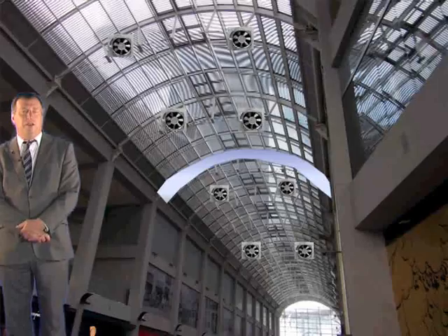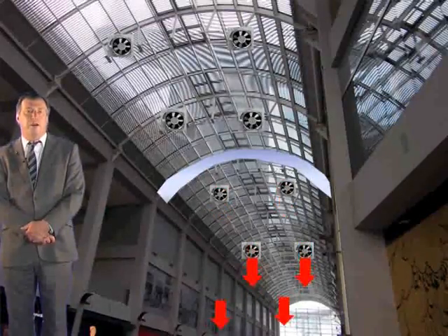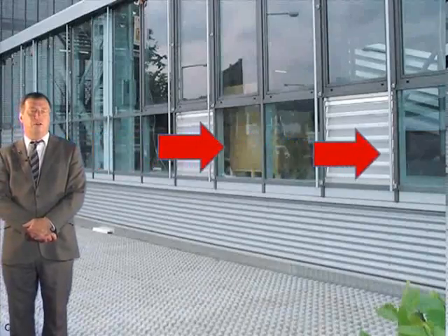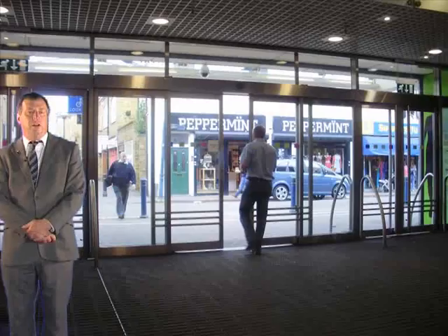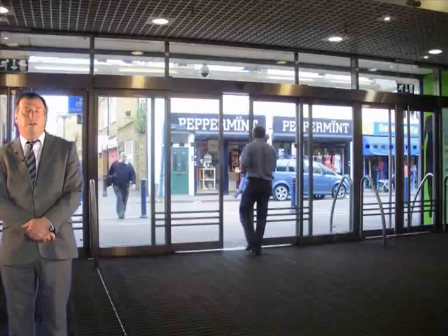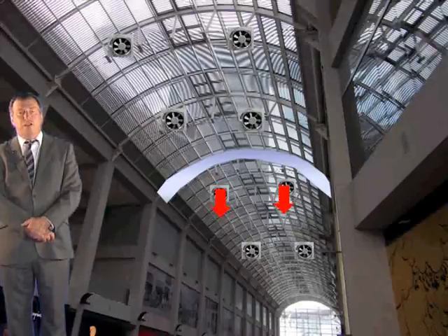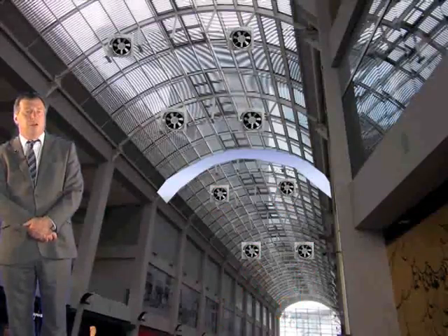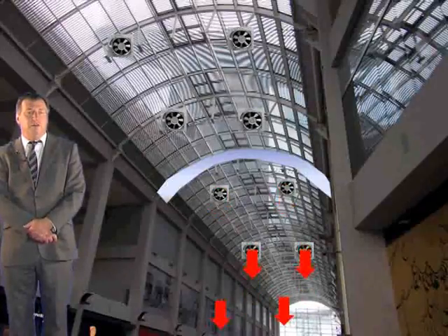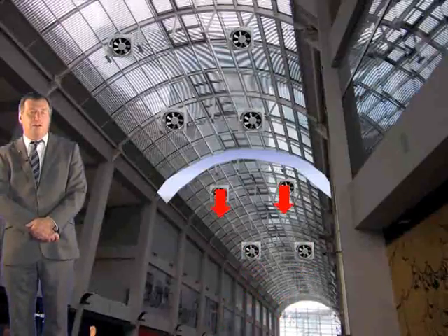These might be the ventilators in smoke reservoirs that are unaffected by the fire, or they may be automatic opening vents located at low level in the walls of the building, or they might be the doors that are used for means of escape, doors that automatically open on actuation of the smoke control system. Natural vents in unaffected smoke reservoirs can often be opened automatically at the same time as the vents in the reservoir that is affected by the fire, and these provide replacement air.